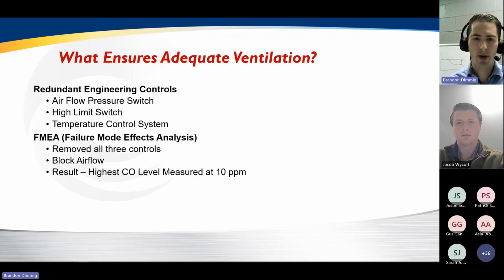So then the question is, what happens if one of these safety controls fails? We did a failure mode effects analysis where we removed all 3 of the safety controls. We took away the airflow switch, the high limit, and the control system, and we blocked the airflow through the unit. And we said, well, what would happen in the absolute worst case that all 3 of your redundant controls fail? And in fact, we found that the highest carbon monoxide level discharged was 10 parts per million. Again, that's quite a bit lower than the permissible exposure limits for carbon monoxide. So there are a number of things at play here, not the least of which is the safety certification, but really just from a design standpoint, that ensures that these units are safe.